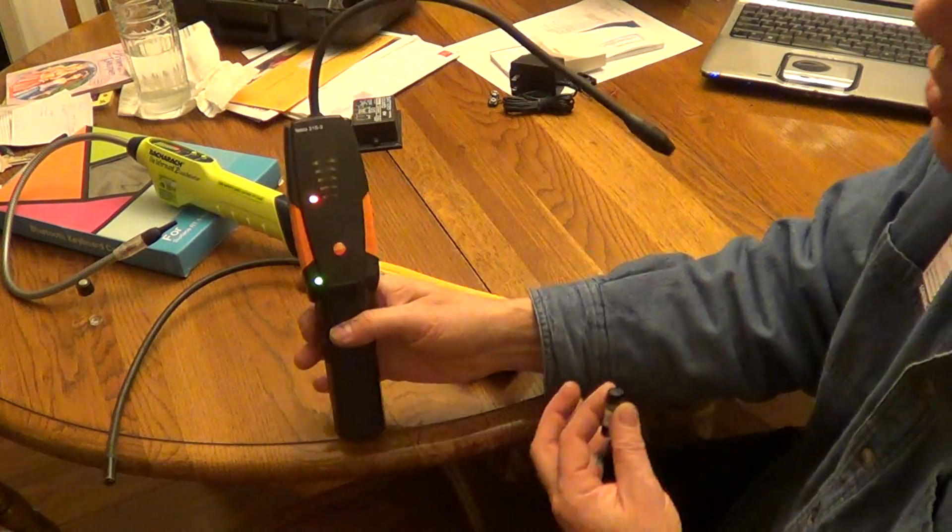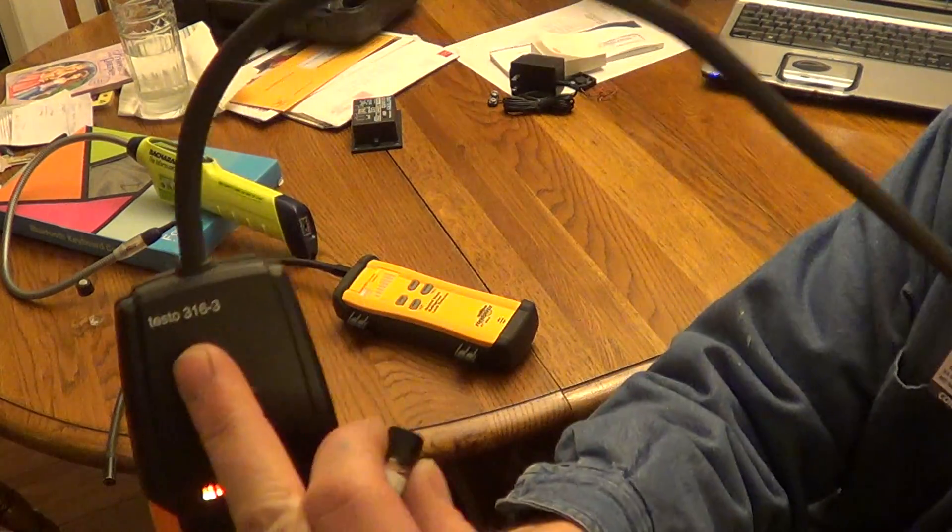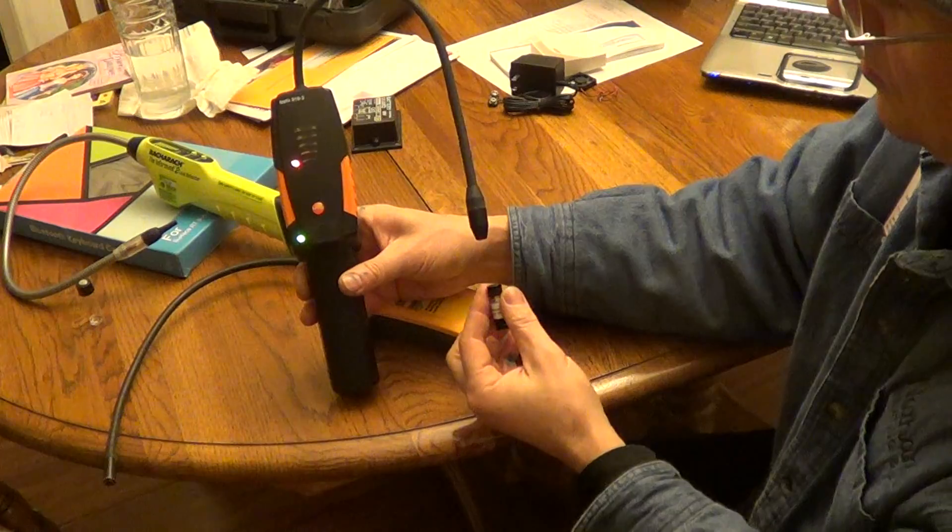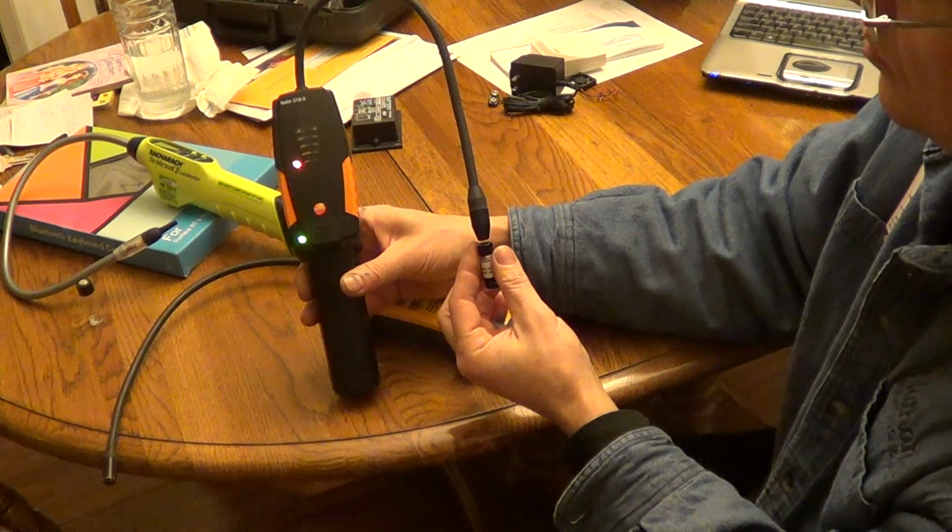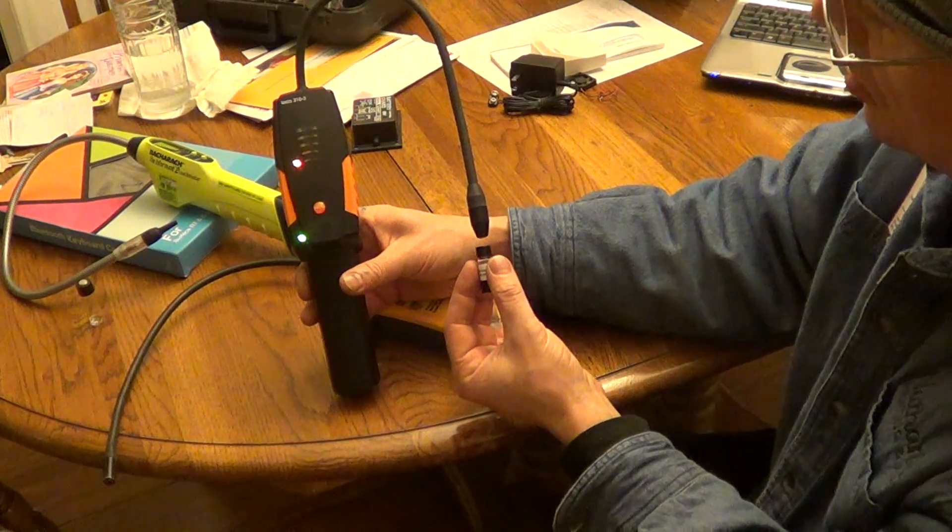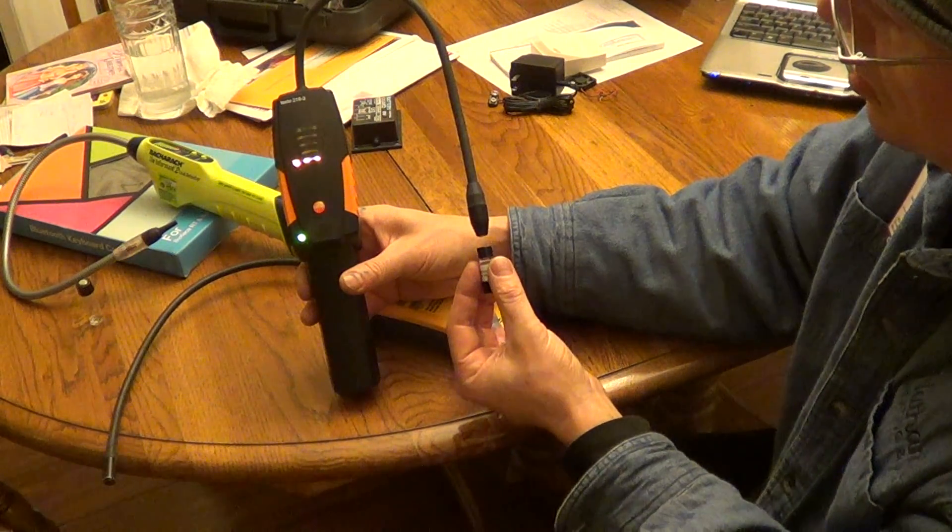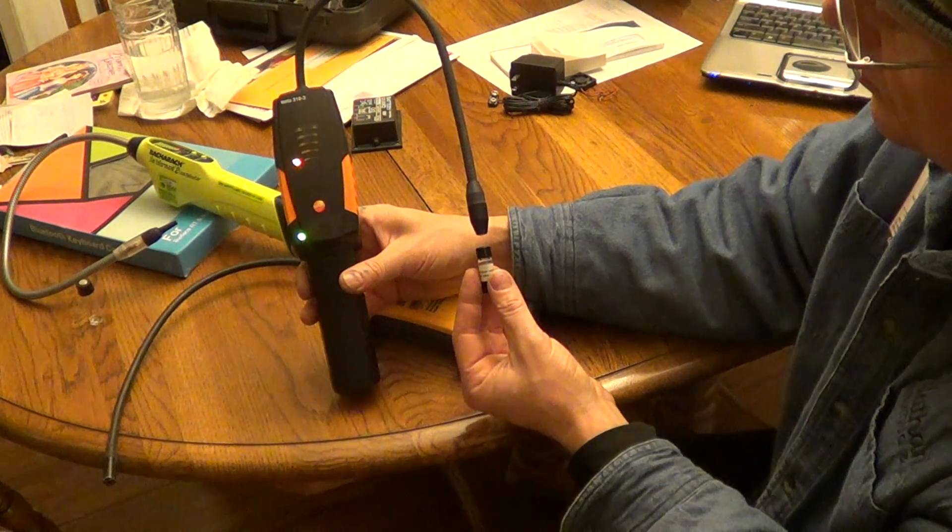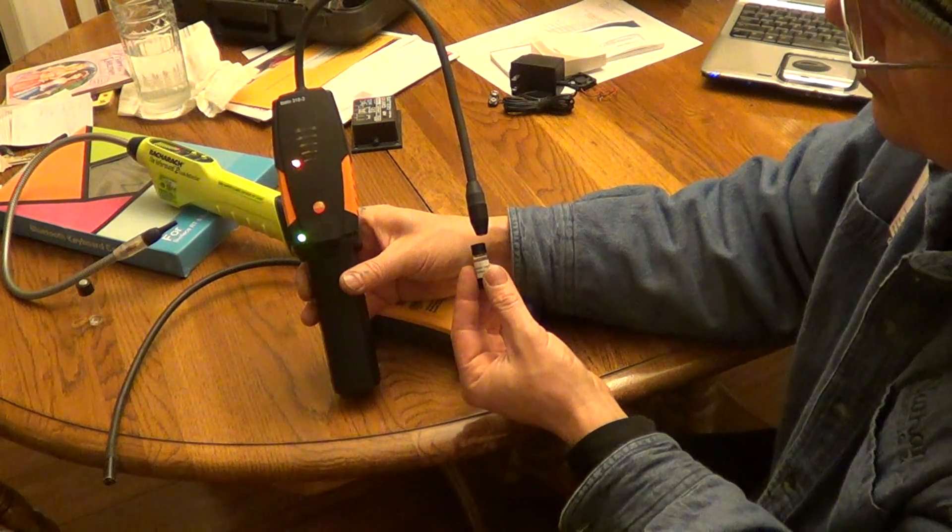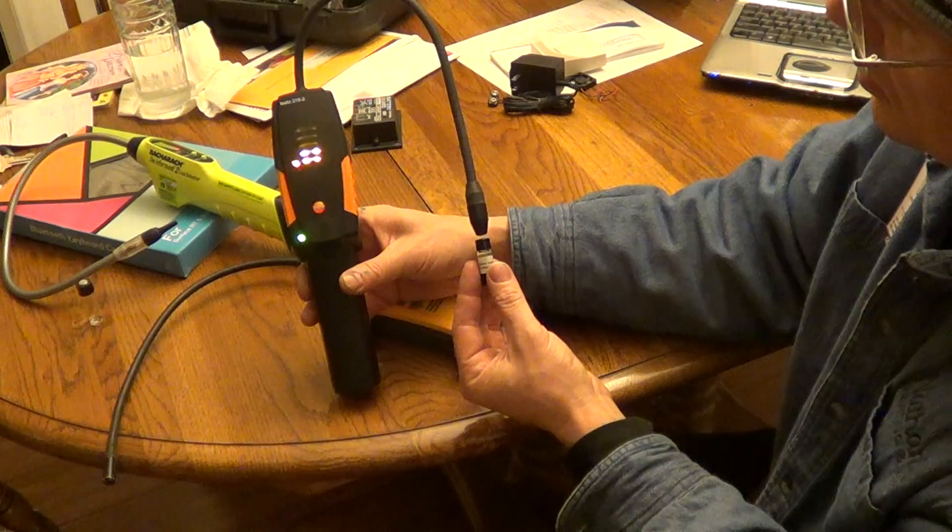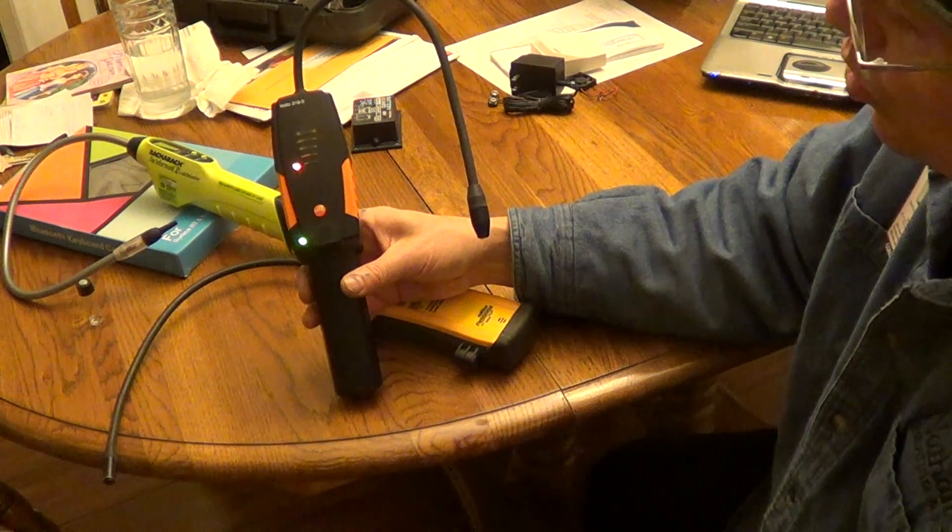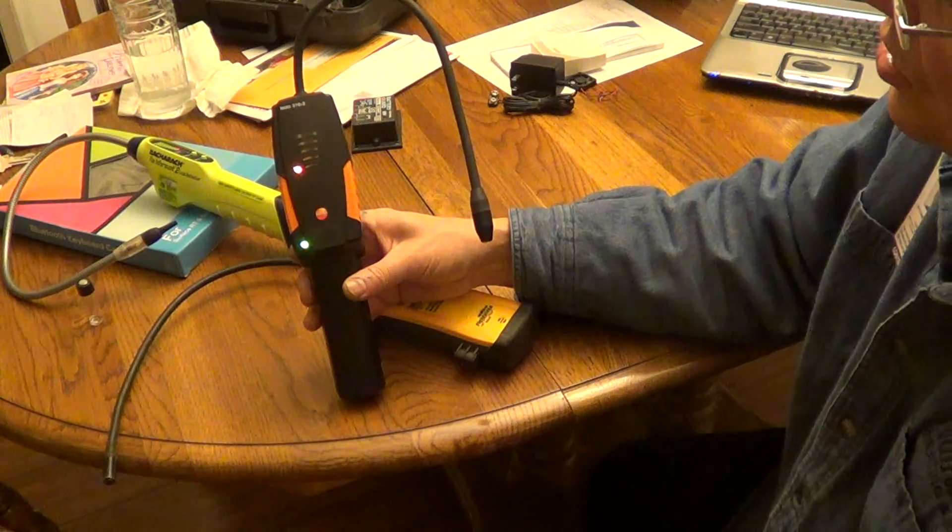Okay, Testo. This is a 316-3. Okay, it looks like it's about a quarter inch. It picks it up. So on the HFC, about a quarter inch. And it's not nuisance tripping at all.